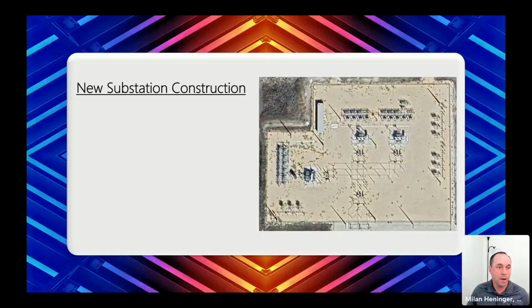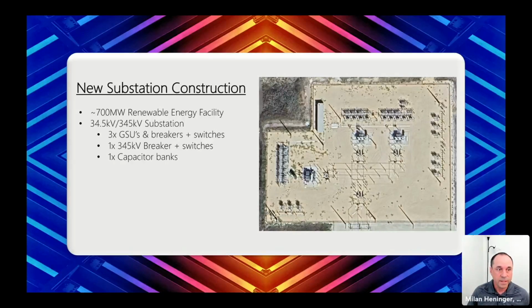It was a 700 megawatt renewable energy facility located in Texas. This substation is a 34.5 to 345 kV. It has 3 generator step-up units with all their associated breakers and switches. There is one 345 kV breaker and associated switches, and also a capacitor bank in this sub.